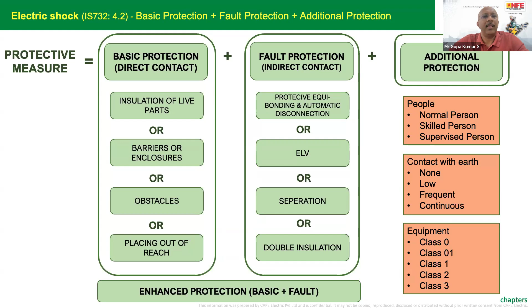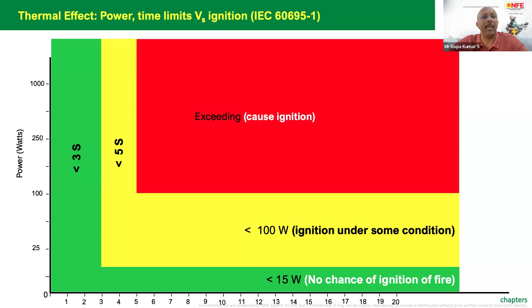This being the fact, for example, protection against fire: the basic idea is that 15 watts, even for a longer duration, could not ignite fire. 15 to 100 watts for a longer duration, maybe it can ignite fire. Any fault where the heat produced is more than 100 watts for more than 5 seconds is fatal. It could create fire. You can find this information in the standard. So basically, automatic disconnection is what is required.